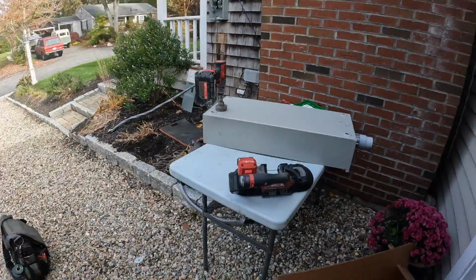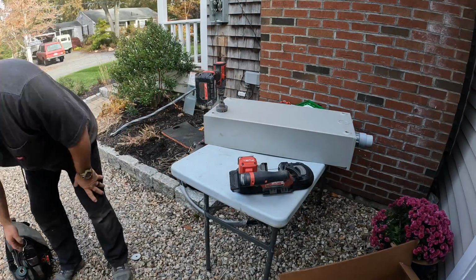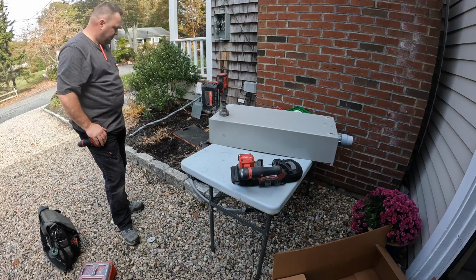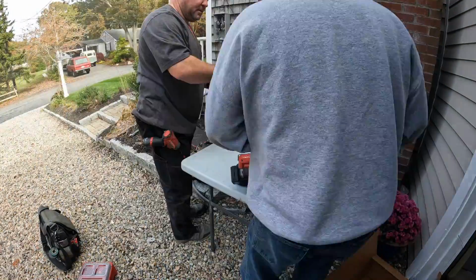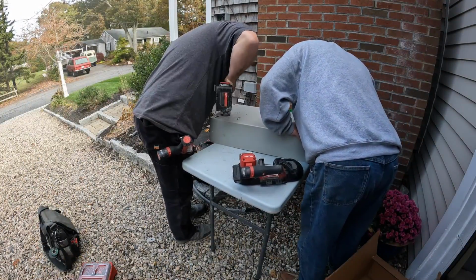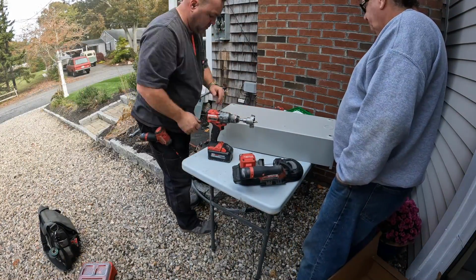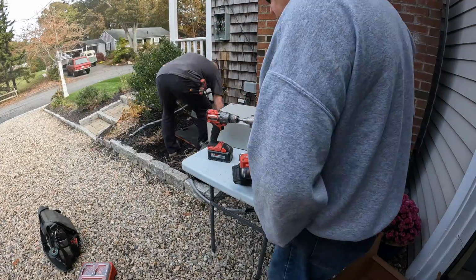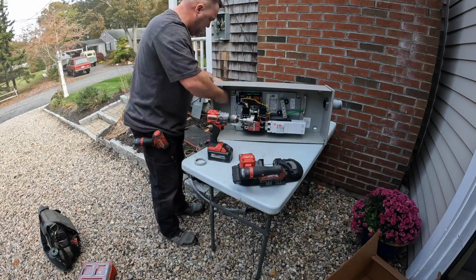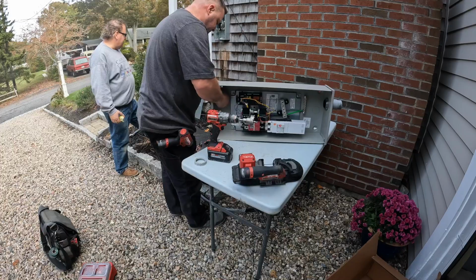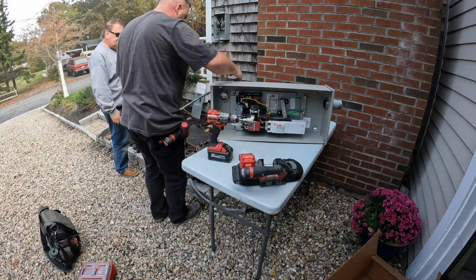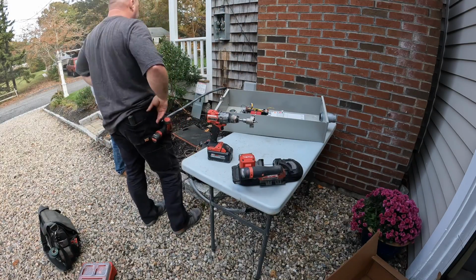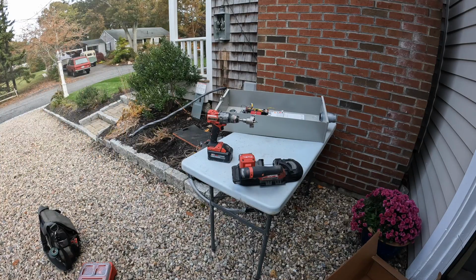And so that's what I'm working on here, and I'm measuring and figuring these things out a little bit at a time. There is only so much room to get these cables into the back of this transfer switch, because obviously the lower I go with the transfer switch, the less of a chance I have to find that rim joist to bring my wires through. So I'm making the knockouts in the transfer switch, and then I'll mark them on the house before making the holes in the rim joist and sliding my wires through.